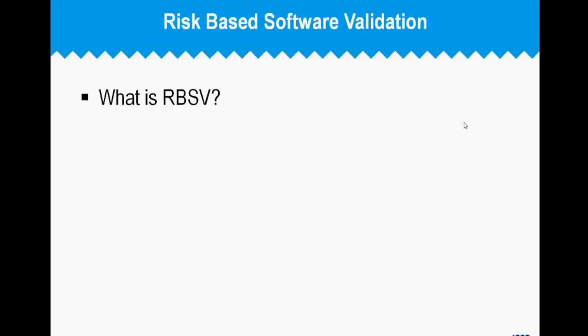And so that becomes an issue of taking a look at what the agency has talked about around how to do risk evaluation and focusing that particular approach on your particular product, and using that to drive what the priorities are, what the risks of this product are, and focusing your efforts on confirming that your product and your processes are working to address those particular needs. We did this quite a bit at iCardiac. You want to talk about that, Jamie?